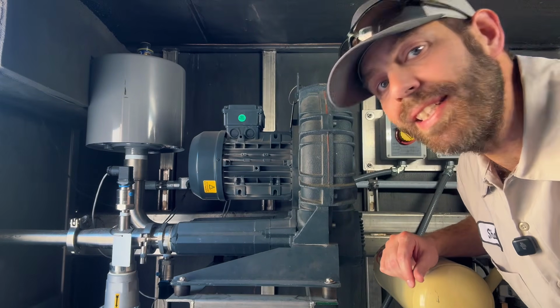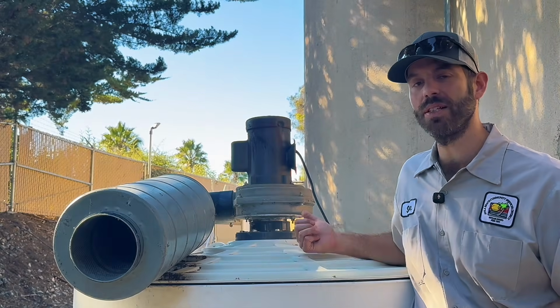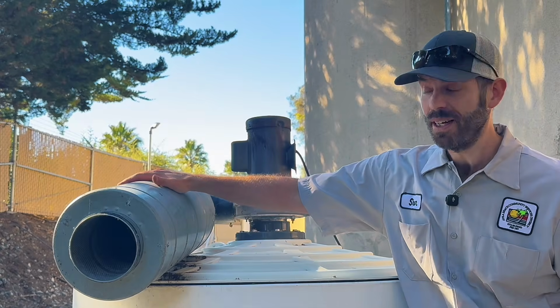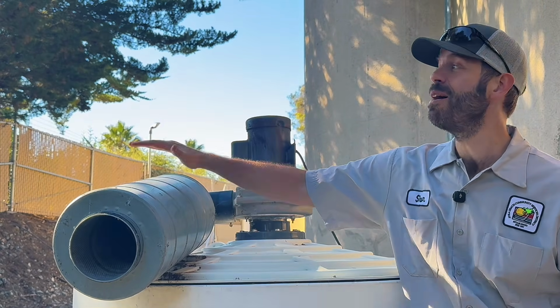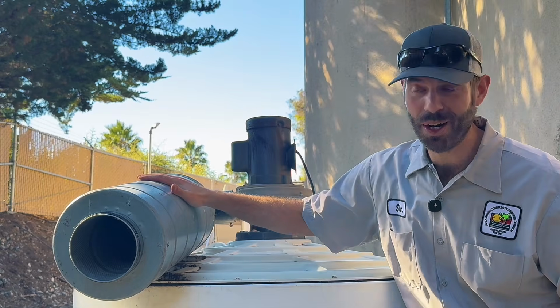And with that, let's head over to that scrubber and take a look at that blower. What you see next to me is a centrifugal blower on our odor control scrubber. This is a muffler. It's not a big cannon, it's a muffler because there's houses right over there and this thing makes like jet engine noises when it's not on there.